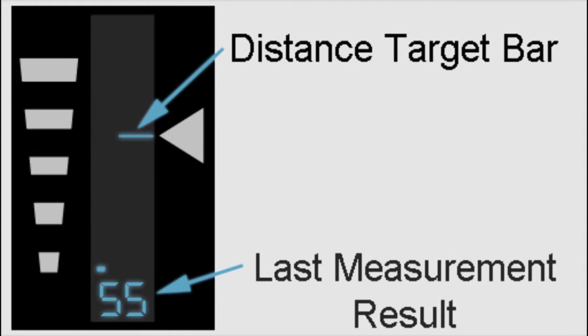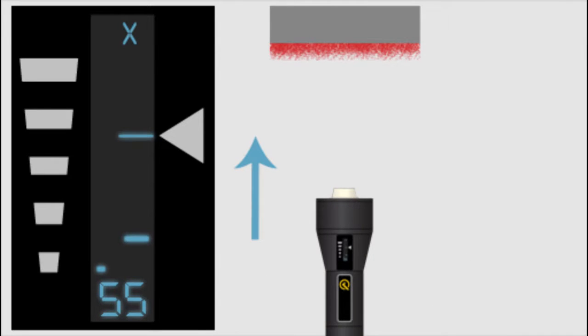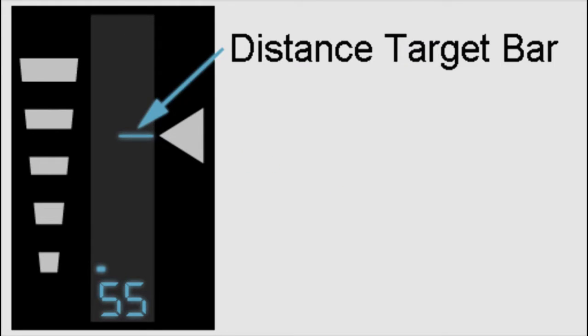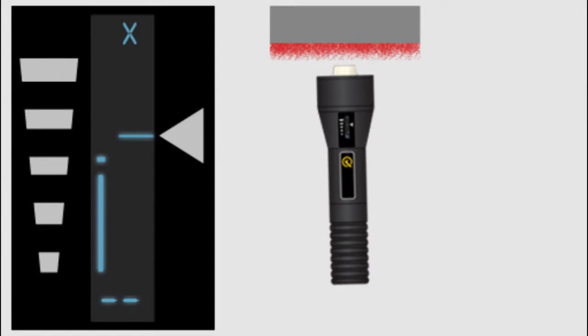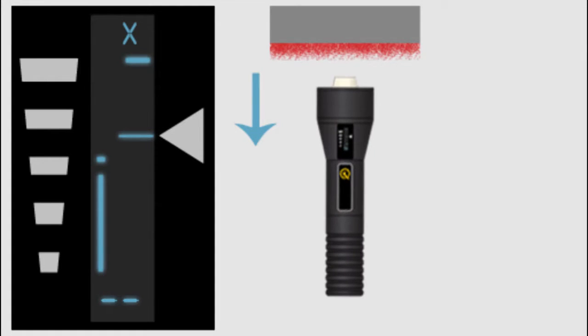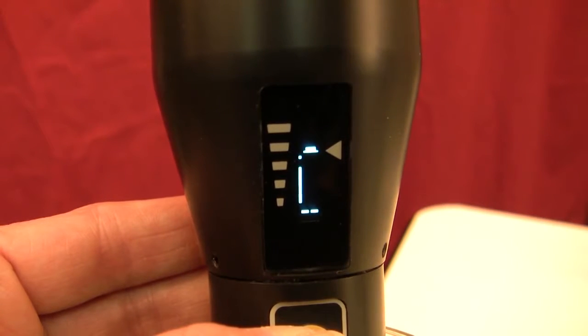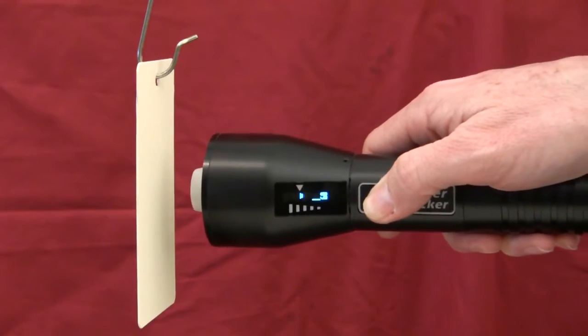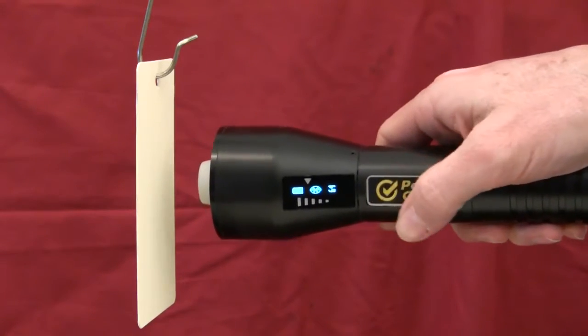When the button is pressed, the instrument begins to acquire samples and the display changes. As the probe is brought closer to the powder, a distance paddle appears. Here, the paddle is below the target bar, so the probe must be brought closer. Here, the paddle is above the target bar, indicating the probe is too close to the powder and must be moved away. For best results, allow the distance paddle to move to either side of the target bar. This will happen naturally if parts are moving.